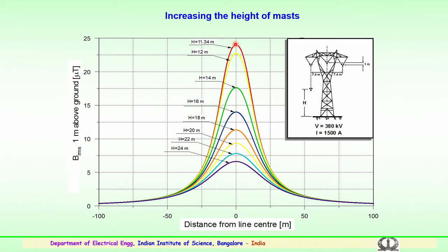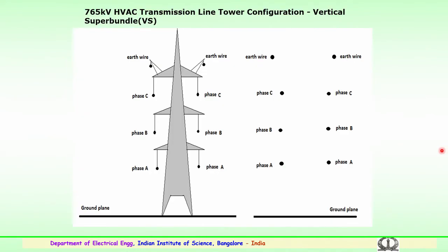So this shows that increasing the mast or the clearances could bring down the magnetic fields, particularly near the ground surface near the high voltage or extra high voltage tower, which is carrying more power. And it should also be noted that magnetic fields, as mentioned earlier, mainly depend on the current carrying capability of the conductor. So the magnetic field will be more only when the current is very high. When the voltage is very high, the current is less, so magnetic fields are not of much concern; electric field is of concern. As the power transfer goes high and the current load is higher, the magnitude of the magnetic fields also goes high.